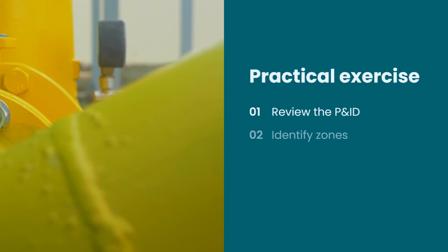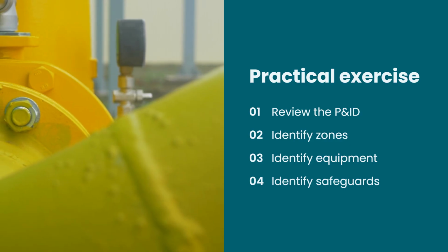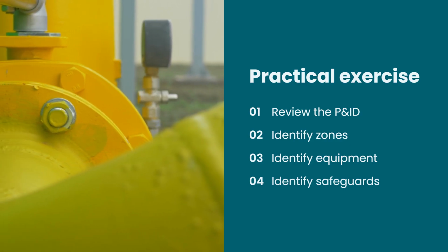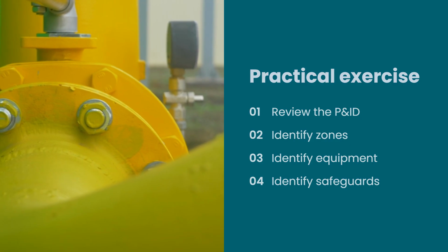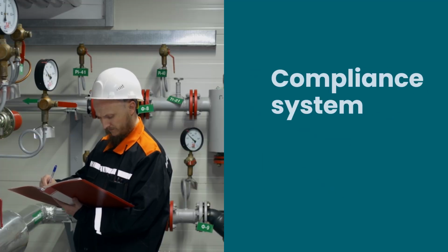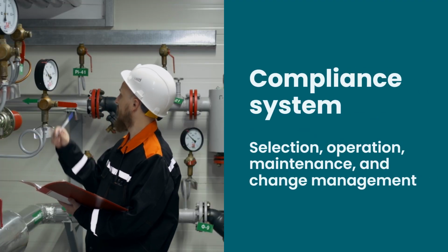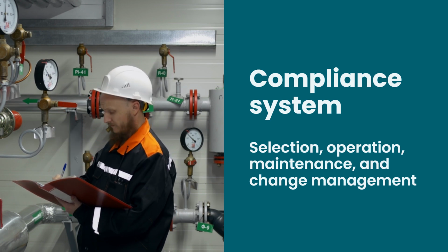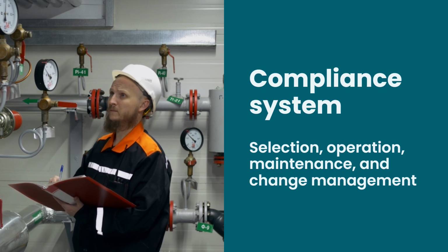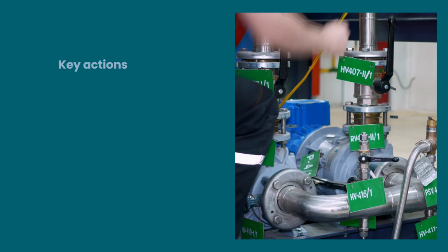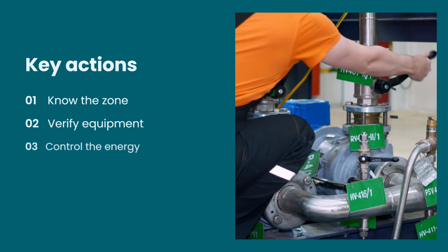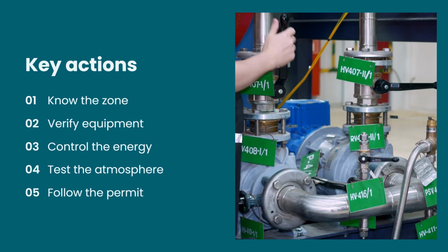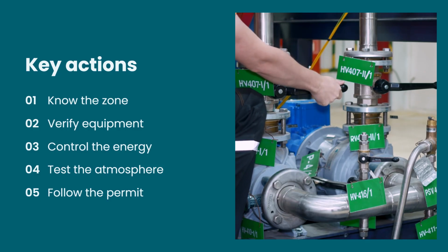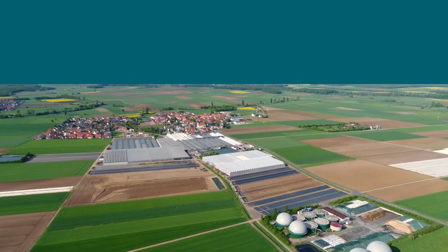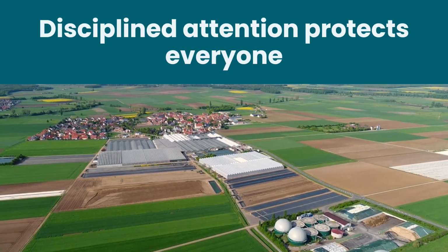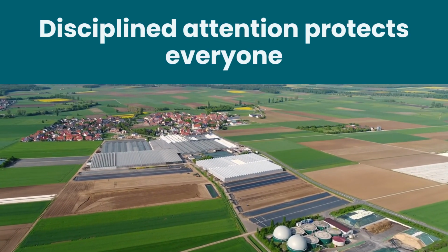For the practical exercise, review and approve biogas drawings and identify zones, equipment, ignition sources, and safeguards. ATEX compliance is a system of decisions made during selection, operation, maintenance, and change management. Know the zone, verify the equipment, control the energy, test the atmosphere, follow the permit. In a biogas facility, disciplined attention protects the process, the equipment, and everyone working nearby.